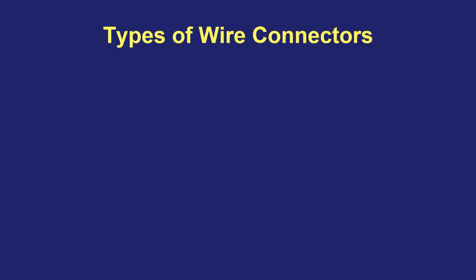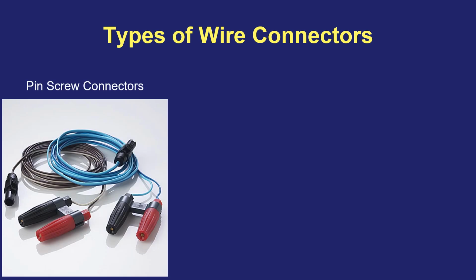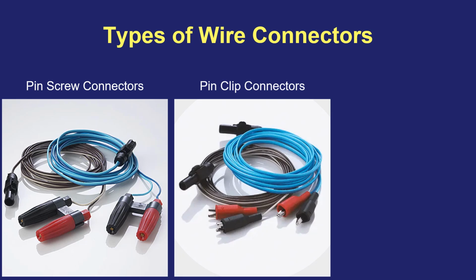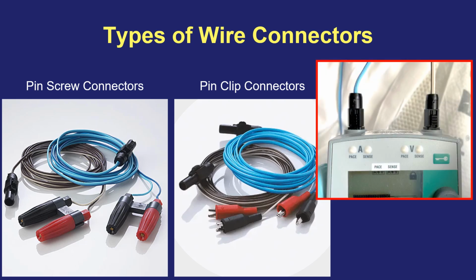And just to, again, review those different types of connectors, here are these screw type connectors that hook up to the pins that I showed. Here are a very similar set of wires with the same color scheme, and of course the same ends that plug into the temporary pacemaker box, but you can use alligator clips to hook up to the pins. This is maybe less secure and could potentially fall out as opposed to the screwed in version, but this would allow you to hook up a second one to a skin electrode, for example, if you needed a needle in an emergency like I just showed. And again, in both cases, the atrial and the ventricular ends, of course, will plug into the pacemaker box in their respective channels.